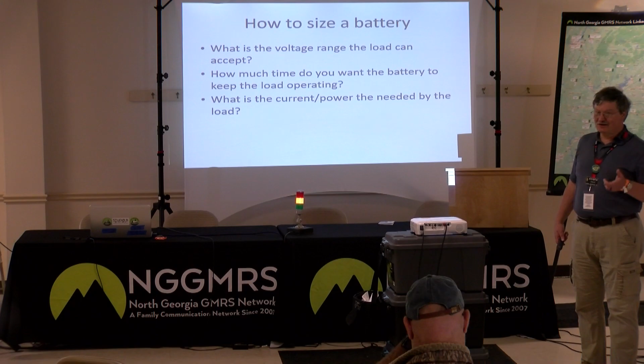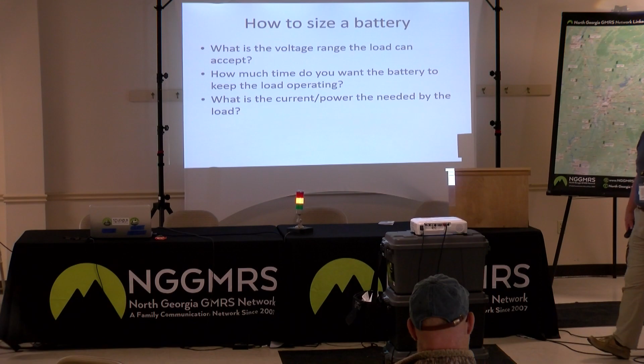You've got to make sure your equipment is capable of providing that current. Because if I need 100 watts, do I need 100 watts at 1 volt, which means 100 amps? Or do I need 100 watts at 100 volts, which is 1 amp? Quite a bit of difference in the cable sizes for 1 amp versus 100 amps. And that affects your battery stuff too when we get into it.